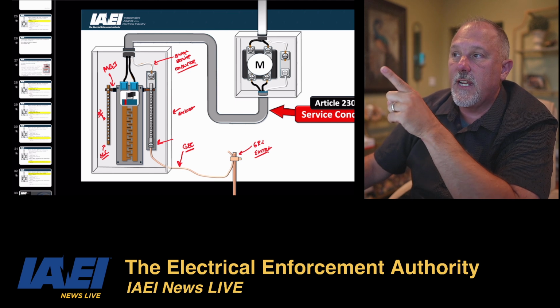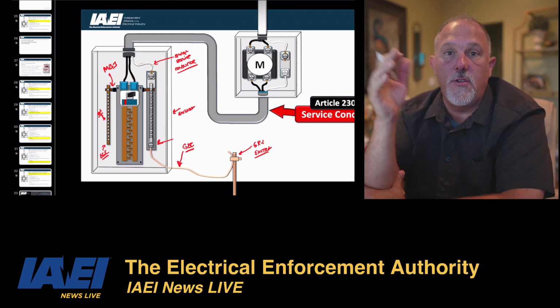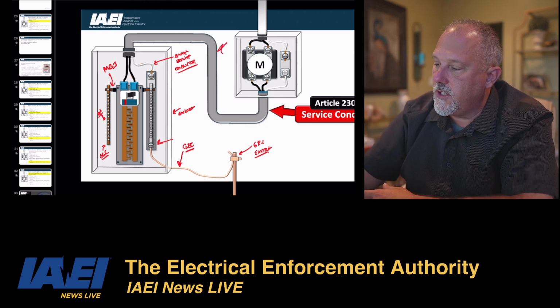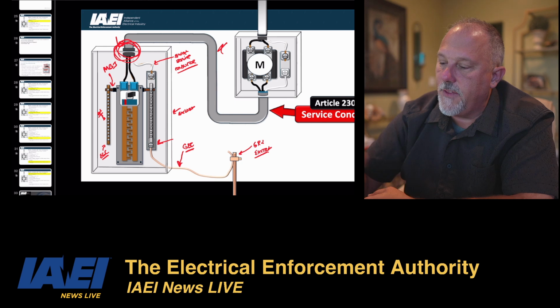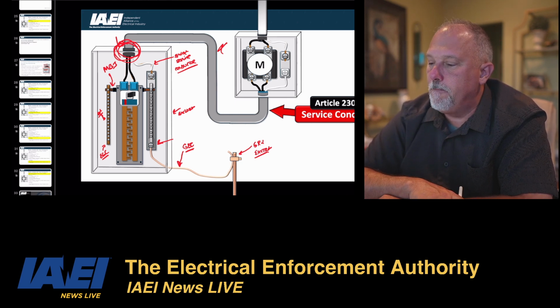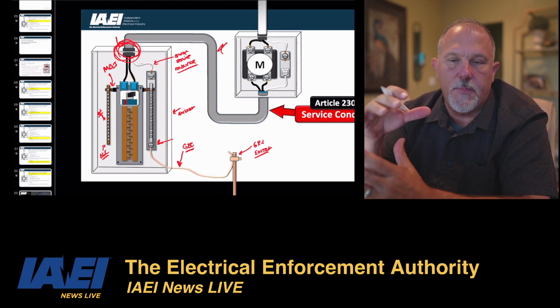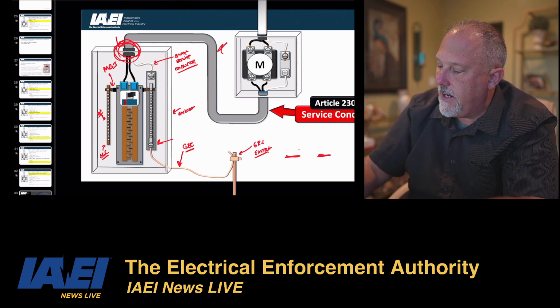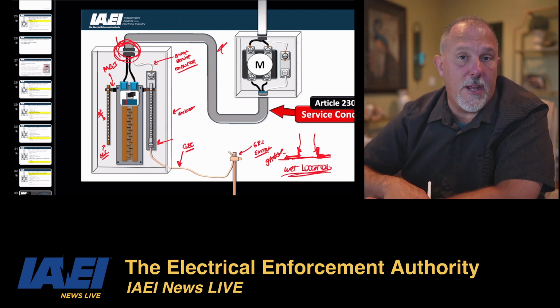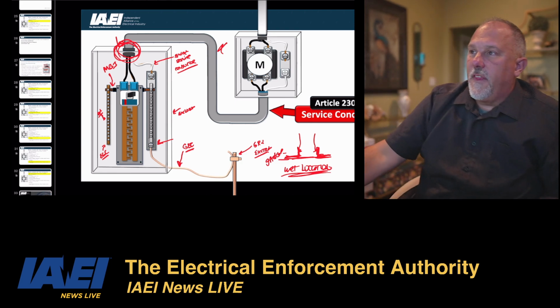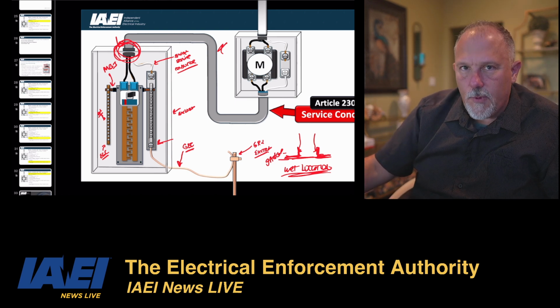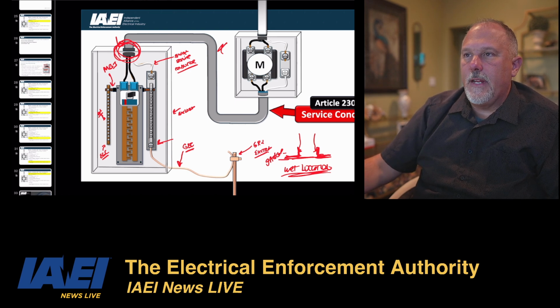250.92 services. Take a look at the bonding requirements. This is going to tell you what can and cannot be used when you're connecting all of these raceways together. The fittings here, and what types of knockouts you have. Typically we'll put that Myers hub type in there where you have the flat plate, like this, and then there's threads, and your conduit threads in that way. This is gasketed, and it's listed for a wet location because it's probably going to be on the outside of the house. All right, so you've got to think about your bonding, how you're connecting your raceways, etc. That's 250.92.